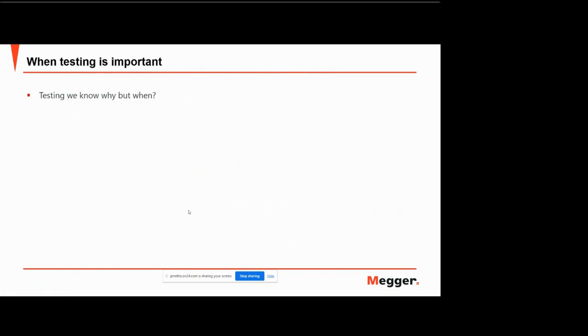Okay, so those are some of the main points we've covered with why we need to test, but when do we actually need to test? So during commissioning, if you're introducing new assets into your DC network, you need to make sure that they operate as predicted and to specification. And for any line upgrades, as we've mentioned before, as we increase the current demand on lines by upgrading to cope with the increasing number of trains that are running on those lines, we need to make sure that the protection scheme that's supporting that upgrade is also capable of coping with that additional increase.